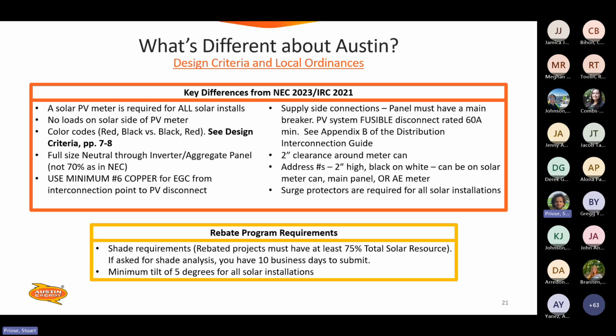so that you've created a received read on that PV meter, and that's because we have value of solar, and all of the solar production needs to get credited to the customer before it serves any loads or goes back to the grid. Our color code you'll find is different than pretty much anywhere else, which is red for residential services. It's going to be line 1 red, line 2 black, as opposed to black, red, which you're used to seeing. So you can see in the design criteria manual that'll spell that out.